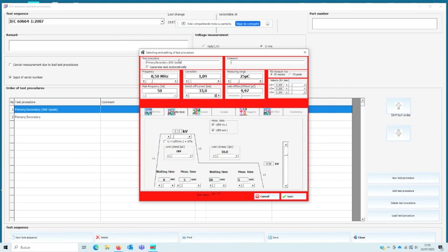So as we are considering this component that should work at a maximum working voltage of 850 volts peak, it means that the maximum voltage that could be between primary and secondary side would be 850 volts peak. The voltage that we are defining here is defined in RMS. So according to the conversion, the equivalent voltage would be 600 volts instead of the 850 volts peak. So here, if we multiply the 600 volts by 1.875, we would have 1.1 kilovolts, and then 1.5 times 600 volts, we will have 900 volts. Okay, so now we will perform the test.